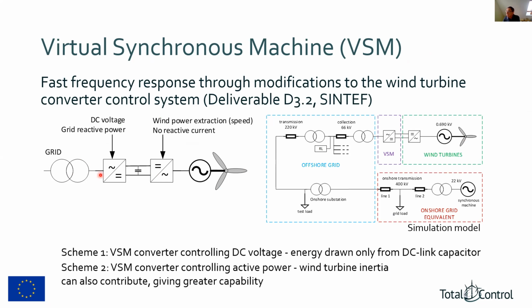They looked at a couple of different schemes in simulation, where they simulated an onshore grid and the wind turbines doing this control. One was using the DC link capacitor to draw energy from, and the other feeding through to the turbine, so you can use the wind turbine kinetic energy to provide power. That's a much more capable scheme because you've got a massive flywheel to make use of. So that was one task completed using simulations.